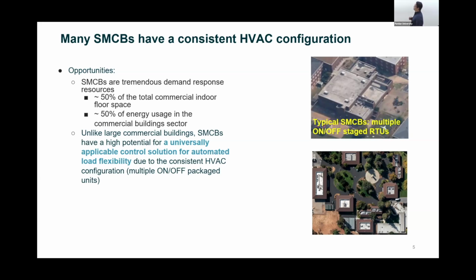The advantage of developing advanced control for this type of system is that the HVAC configuration is consistent across all small and medium-sized commercial buildings, so we can apply the method universally to many buildings having the same HVAC configuration. But there are some challenges because it's a small commercial building. They may pay utility bills of like $1,000 per month, and 20% utility cost savings is just $200. If we install a bunch of sensors, a building management system, and that kind of thing, the payback period could go up to several years, which discourages participants from joining.